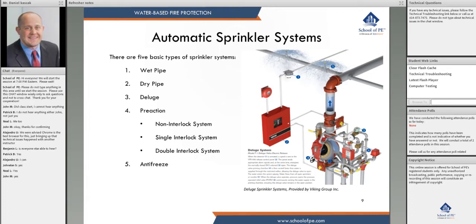A deluge system — shown in this picture — needs a detection system. When a smoke detector goes into alarm, it sends a signal to the control panel, which opens a solenoid valve that releases the priming chamber of the deluge valve, causing it to open. A deluge system has every sprinkler open, so water flows out of every single sprinkler. We use deluge systems in high hazard areas like pool fires, airport hangars, or areas with hydrocarbons.